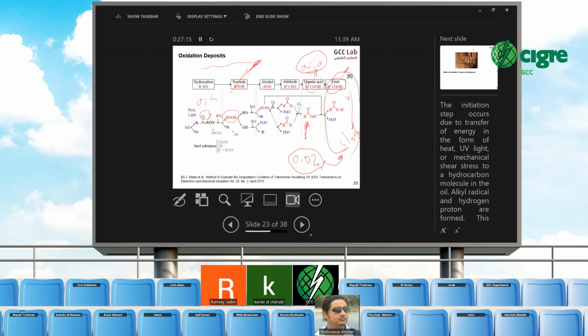Therefore, if you have low acid, and particles and sludge are everything okay, maybe you don't have it now, but be careful that maybe you will get ester, because the time between acid and ester is long. It is a very slow reaction.